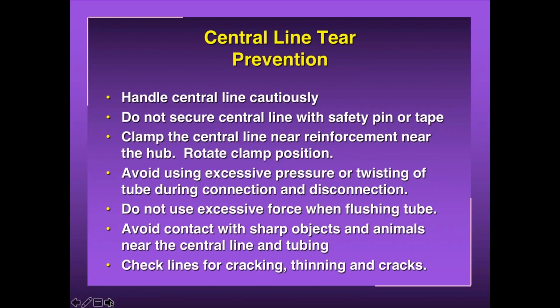So how to prevent it. Be very careful when you handle your line. Don't use any pins or tape or anything on your line. Make sure you clamp the line where it's strongest, near the reinforcement by the hub. And move the clamp from place to place so it's not always in the same position on your line. Don't use excessive pressure or twisting or tightening during connection. And don't use excessive force when you're flushing. And make sure there aren't any sharp objects or animals around when you're handling your line. And then make sure you check your line for cracks and that it looks intact. Next slide.